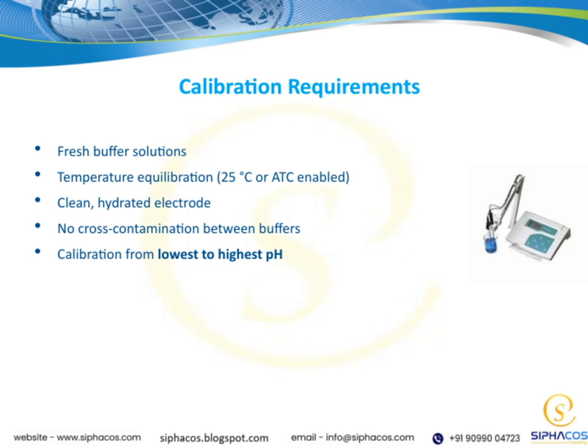First, always use fresh buffer solutions. This helps maintain their stability and ensures reliable calibration. Next, temperature equilibration is crucial. Make sure your samples are at 25 degrees Celsius or that ATC, automatic temperature compensation, is enabled. Temperature variations can significantly affect pH readings, so controlling this is essential.